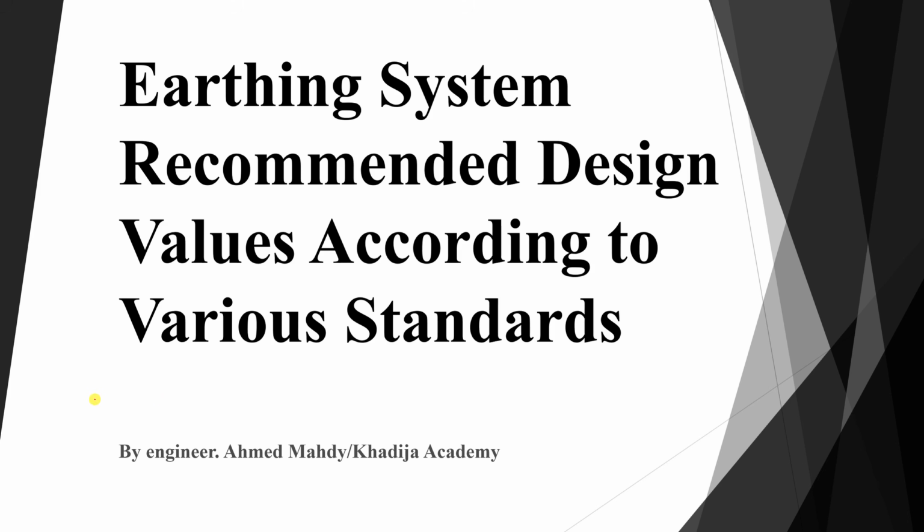So if I am, for example, designing a lightning protection system, we need an earthing electrode system with a resistance of less than 10 ohms. Now, where did this come from and what does the standard say? That's what we are going to learn today.